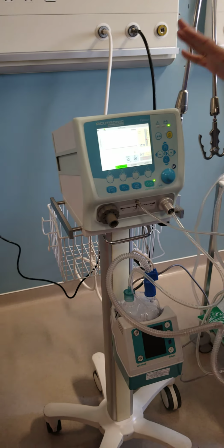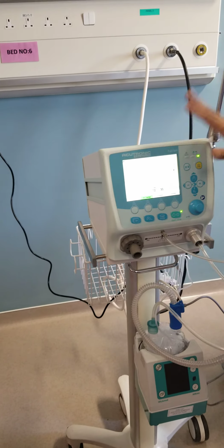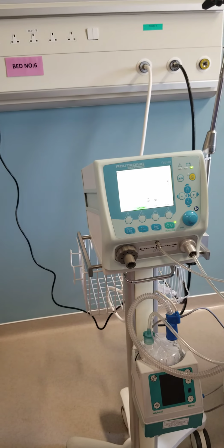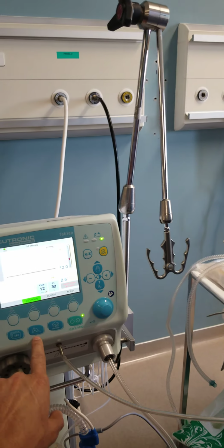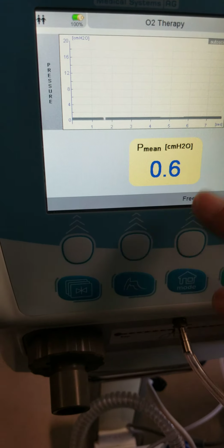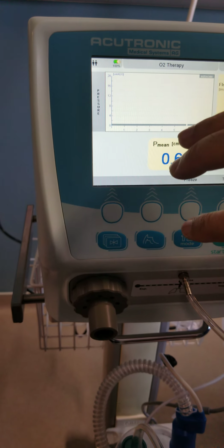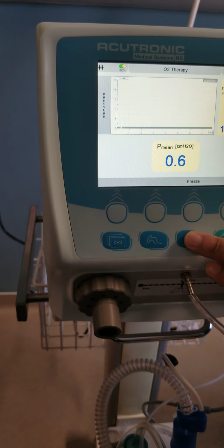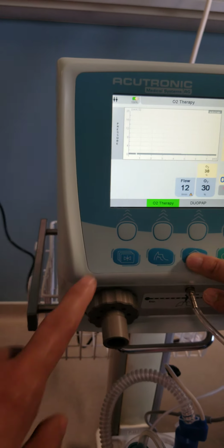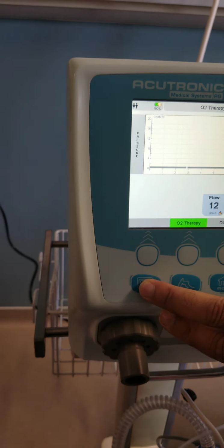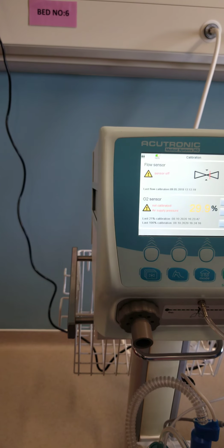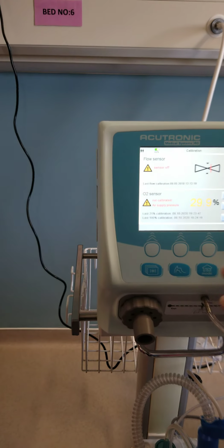So this is how your CPAP machine will be with these three modes. What is this one for? It just gives me a better waveform, shows me, puts it into more perspective. The pressure and PEEP are shown on screen. But otherwise, you go back home. And what about this? This is in case you want to change things. I can show it to you, if you want to do the oxygen calibration in between, or if you want to switch.